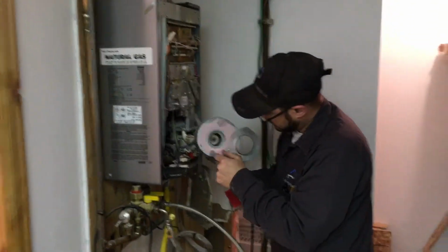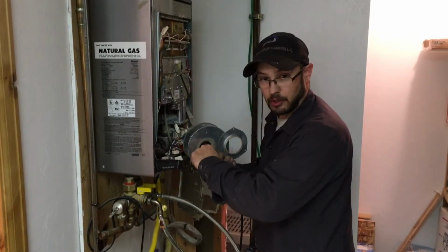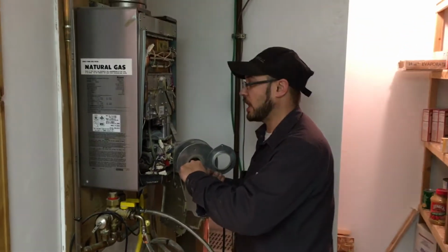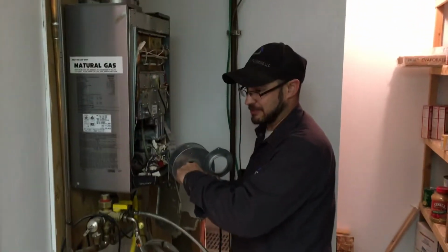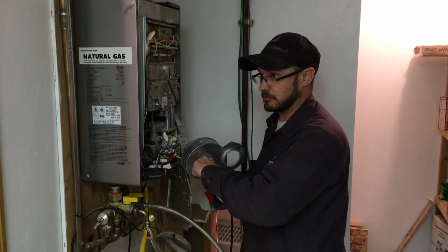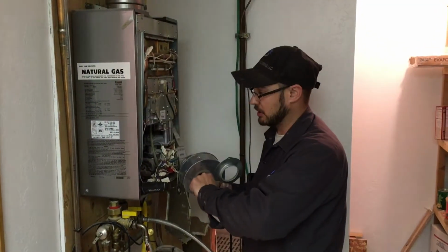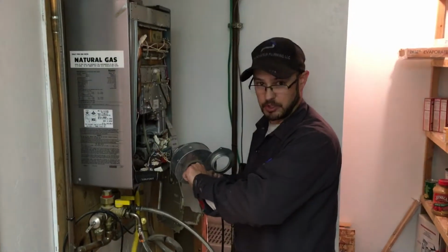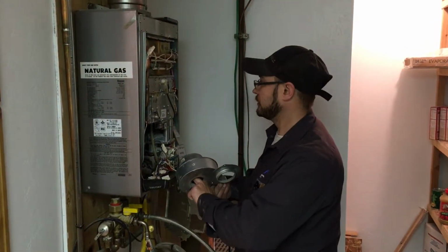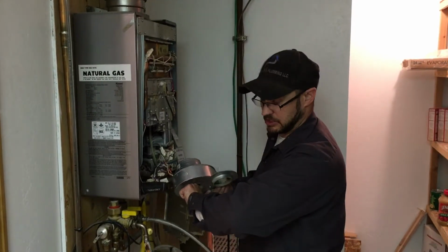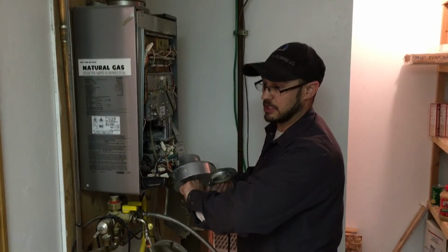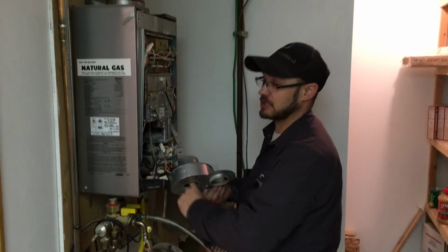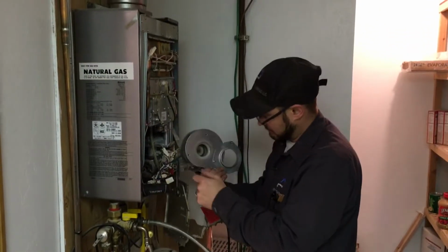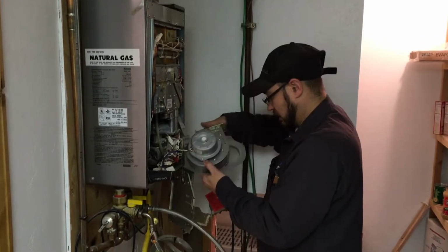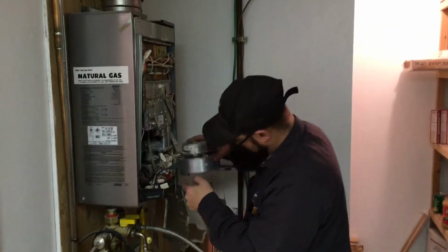The problem was this customer was having a fluctuation in temperature on their water. They'd run the shower and it would go hot, then cold, then hot, then cold, which tells me it's probably a heat exchanger issue — it's not heating directly, it's kicking in and out. You'll have areas clogged up with calcium buildup, so the heat's not heating the water directly, it's heating the calcium, and it's hitting blotches. When it gets blotchy like that, 9 times out of 10 it's a heat exchanger issue. Every once in a while it'll be a fan issue or something else.